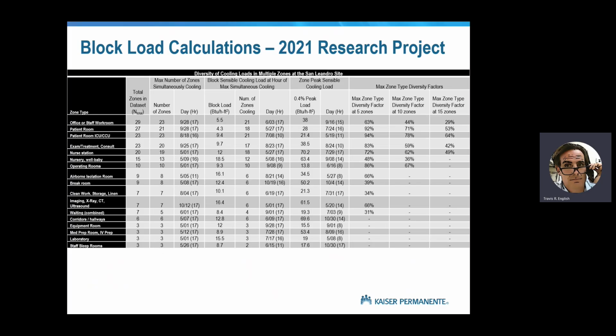Let me repeat that. When we do load calculations, we always assume that similar function rooms peak at the same time. In reality, that is never true. So if you take a look at the top line here, the peak in an office room or zone is 38 BTU per square foot. But when you look at 20 office zones together, the maximum simultaneously occurring peak is 5.5 BTU per square foot. That's a diversity factor of 15%.